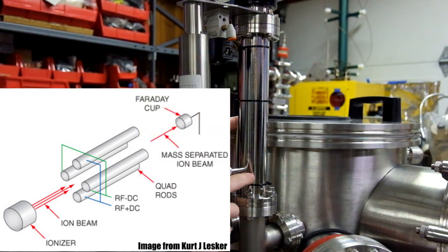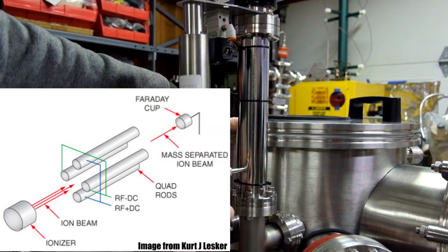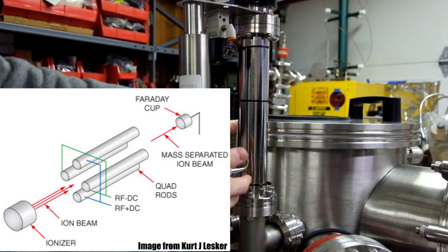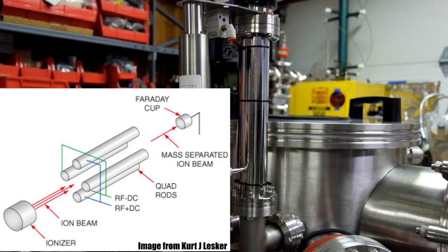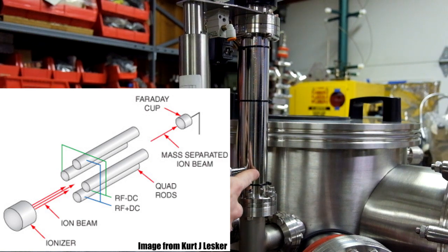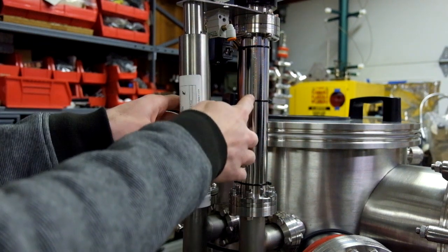Inside there are three main sections: the ion source, the quadrupole, and the detector. The ion source is pretty simple — it normally consists of a filament which generates electrons and smashes those into the residual gas, ionizing it by electron bombardment. Down here you have your ions generated, and they'll be accelerated with a negative potential toward the quadrupole.